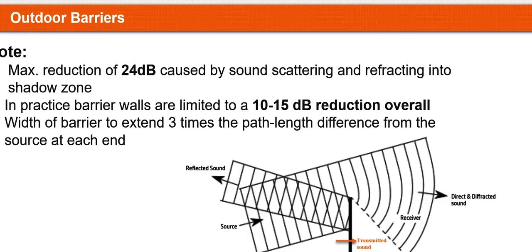Now, most of these barriers are surrounding barriers, so making a full 4-sided wall around the source, or at least a 3-sided one, because if you just use a single barrier, that barrier has to be at least, on each end relative to the unit, 3 times the path length difference from the source. So all of a sudden you have a massive extra long wall, and it's a lot easier and more cost effective to do a full surrounding barrier.